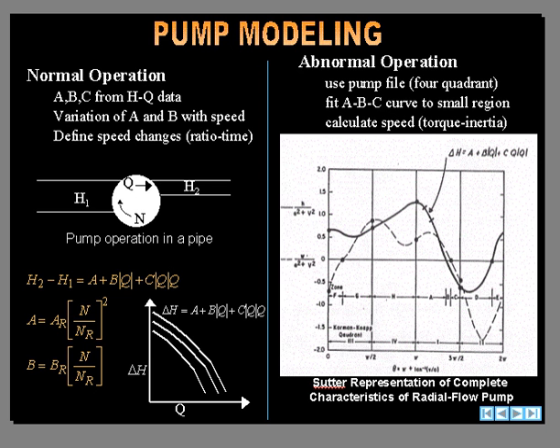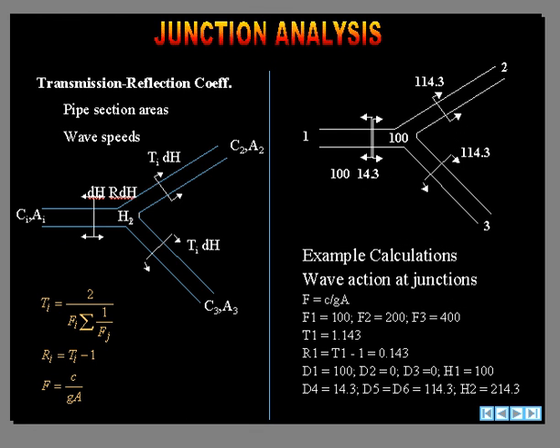For junctions, if a pressure wave approaches a junction, you'll get a transmitted wave into the junction and a reflected wave back. These are quite simple to calculate. Here's an example. If we had a 100-foot wave approaching this junction with these characteristics, this is the wave speed over GA, we would get a wave of 114, actually a magnification of the wave being transmitted down and a reflected wave of 14 going back.